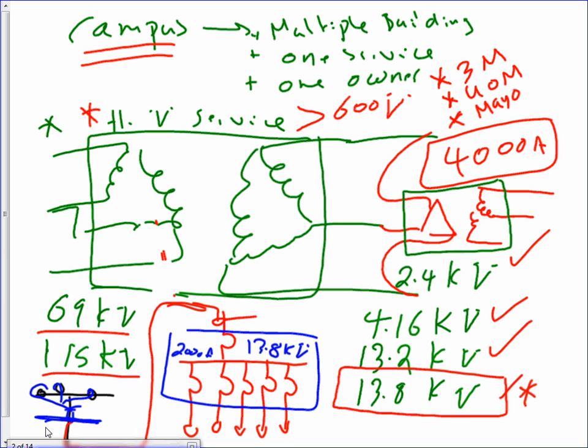They take a high voltage feeder from a switchgear, one feeder per building, and they take all these feeders and feed their buildings. Typically, you get your 69,000 volt into a switchgear. From the switchgear, typically delta, you convert it down into 2.4, or 4.16, or 13.2, or the most common one, Adam, that you're going to be dealing with, something called 13,800 volt. That's the voltage that they use. So they bring it to a switchgear, guys.